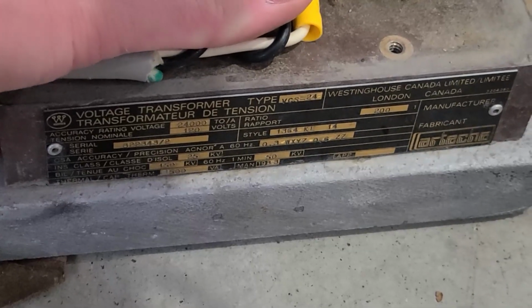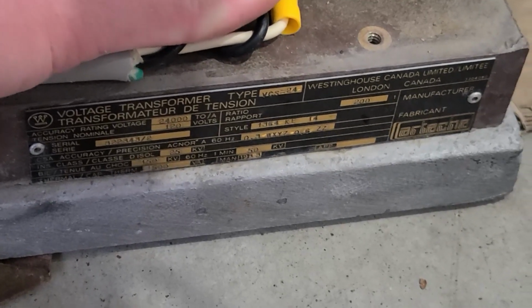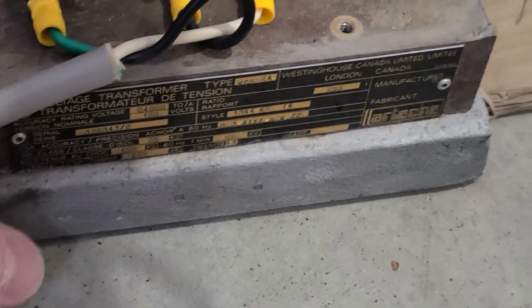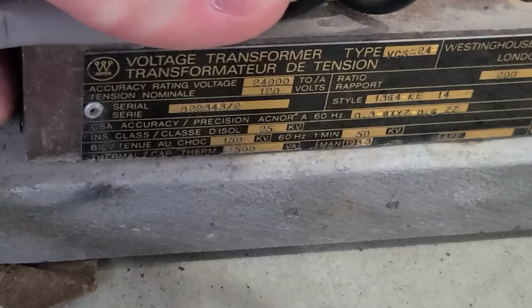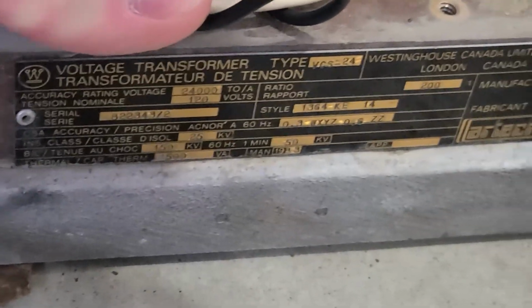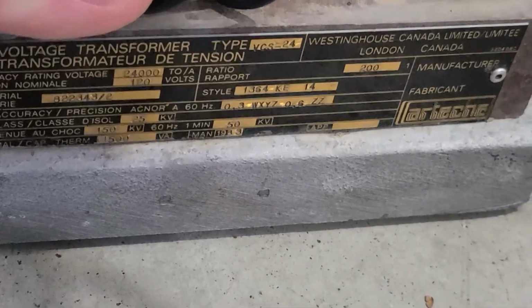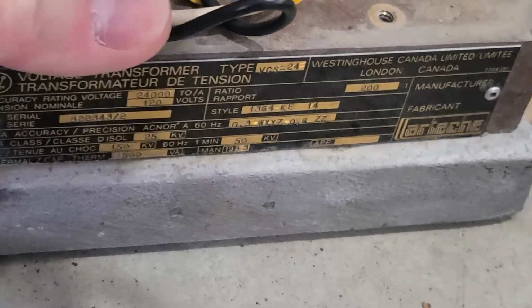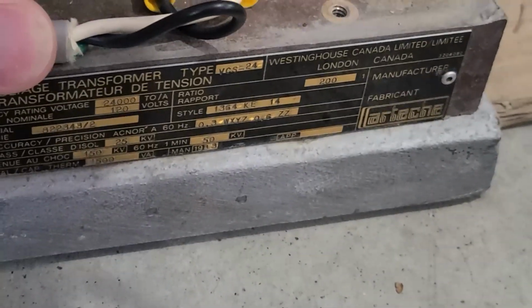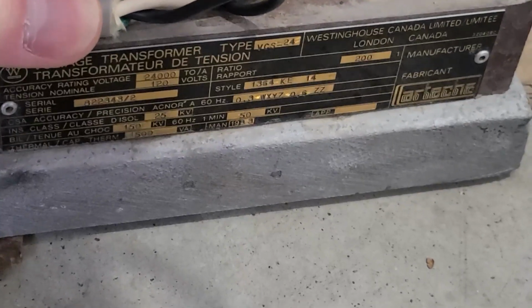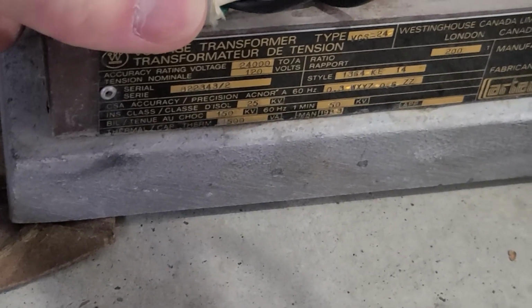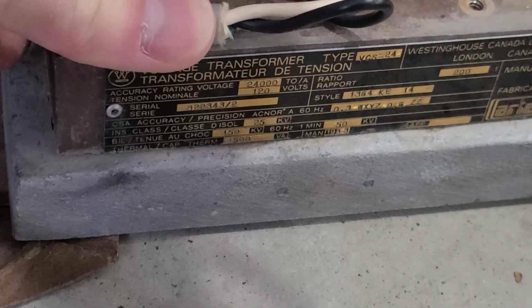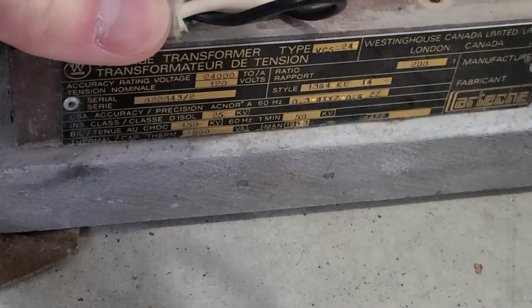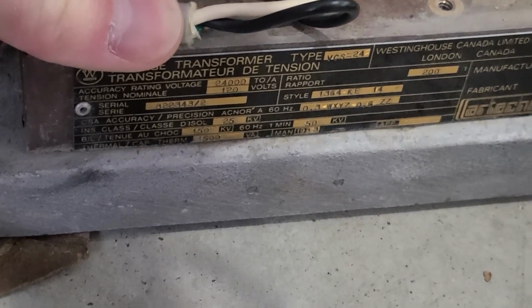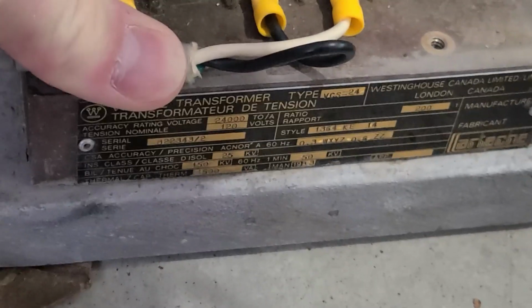It's a 24,000 volt to 120 volt potential/voltage transformer. Down at the very bottom it has a rating of 1500 VA and a 200 to 1 ratio, 60 hertz. It's got a good BIL on there, 50 kV at 1 minute, and 150 kV for what looks like lightning impulse or something.